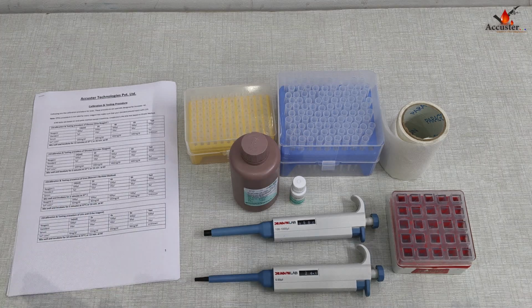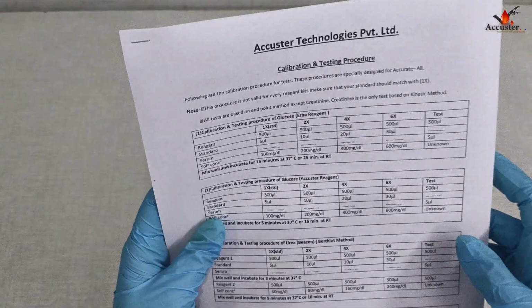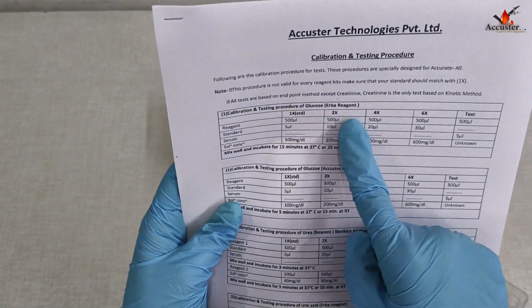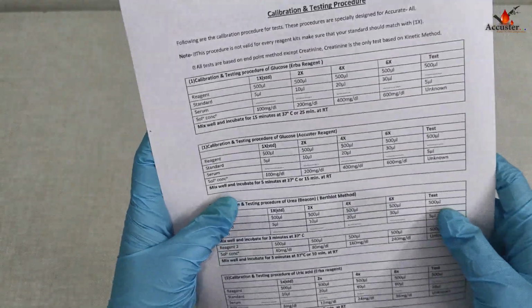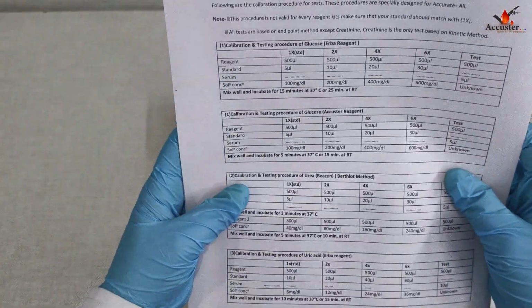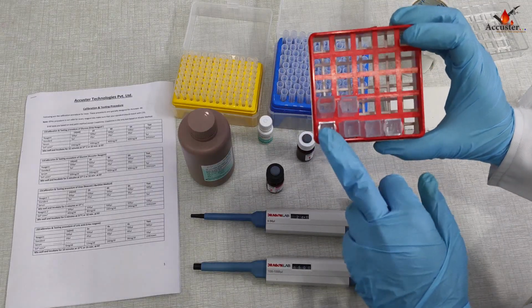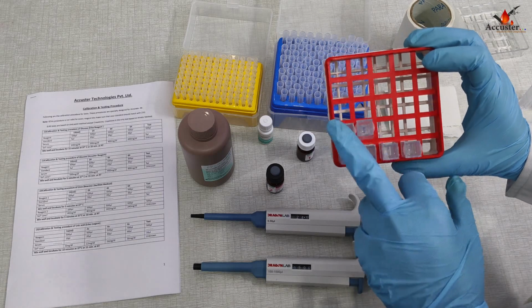For calibration, we need 6 clean cuvettes. Calibration chart, 2 micropipettes, 1 large of 100 to 1000 microliters and 1 small, 5 to 50 microliters. Micropipette tips, both large and small, and tissue paper. Now we'll do the calibration according to the procedure mentioned in the chart. And for that, we need 4 cuvettes for calibration and 2 for control.